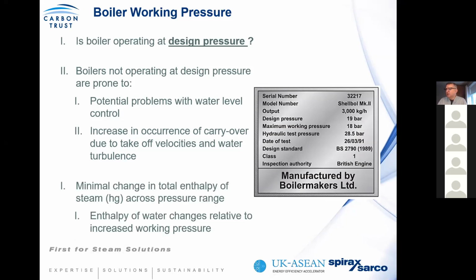Because again, industry has been misled that reducing pressure saves energy. It may do so in a distribution system, hence we're saying reduce to a distribution pressure. But when we look at the steam tables, the amount of energy required to generate steam, say at 1 bar and 10 bar, the difference is very small. So you still require practically the same amount of energy to generate steam at one pressure versus another, but the unrecognized problems with steam quality and water dryness in a steam system are highly determined by boiler pressure. Hence, always operate at design pressure to ensure you have high quality steam to end users. So again, understand your system.